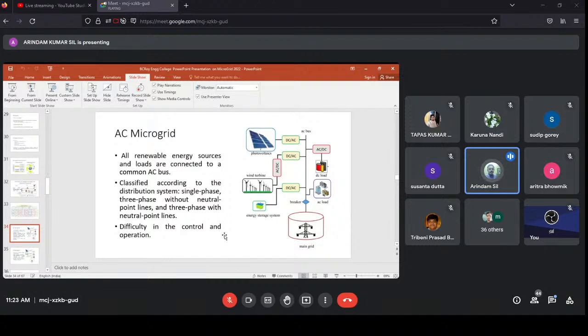We have two types of microgrids. One is an AC microgrid, which has all renewable energy sources and loads connected to a common AC bus, classified according to distribution as single phase, three phase without neutral, and three phase with neutral points. But it has difficulty in control and operation, which is why we need monopolar, bipolar, and homopolar bidirectional power flow controllers. I'll speak about that a little bit later.